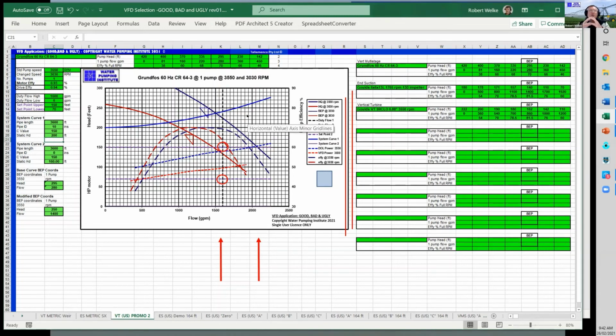In the end, you'll come up with the ideal performance of pump that you need for the job, and then you print that out and send it around to your pump suppliers and say, what's the best you can do for this, to closest to this pump curve. And you'll get feedback pretty quickly. Yes, I can. No, I can't. And whatever they supply the closest, you're going to have to put back into this curve and see what the limitations are for your VFD application. You have to bear in mind the type A, the type B, and the type C for each type of application though. So it's not easy. It's not simple, but it's doable. And this is the software that you can do it on.